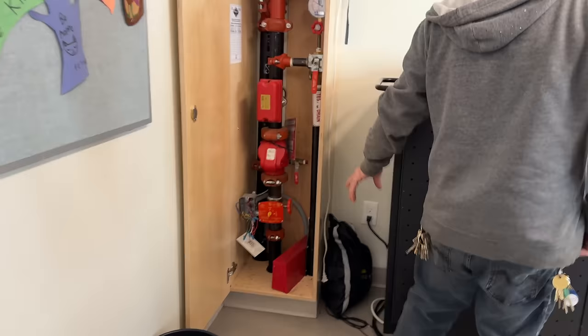We're going to ring the bells to see what area is affected by the short circuit, because we don't actually fully know what is affected by it. So we'll be hearing it for the first time. What's that? For a second, and then it just cut out. It chirped and then stopped. That ain't right.